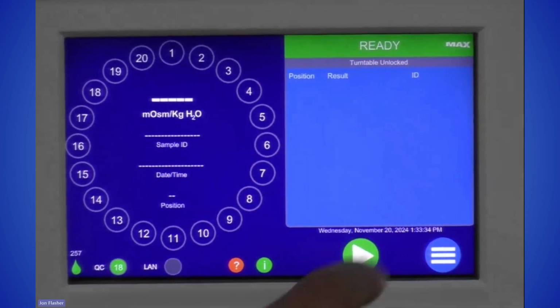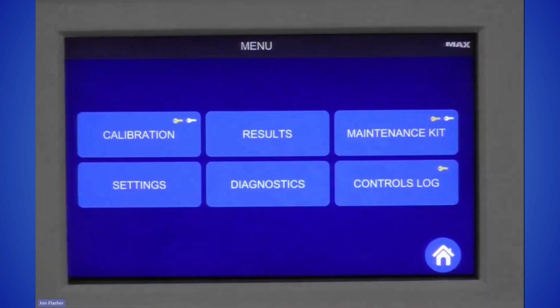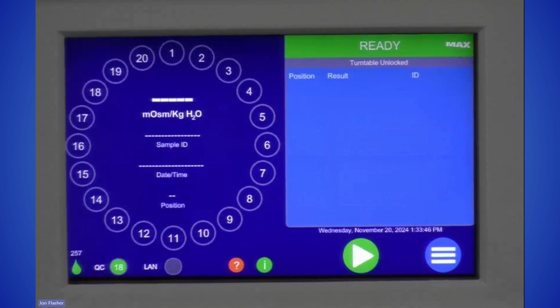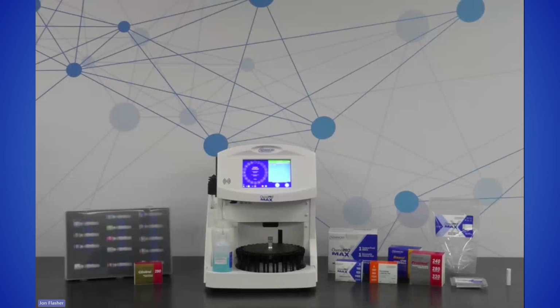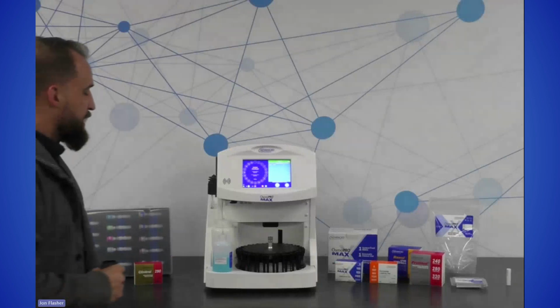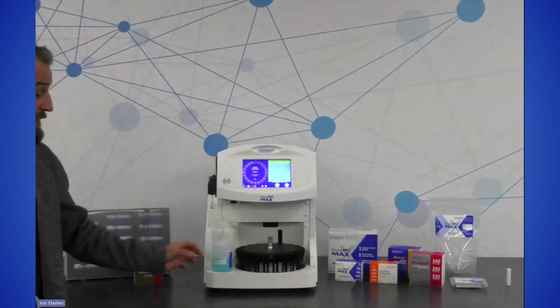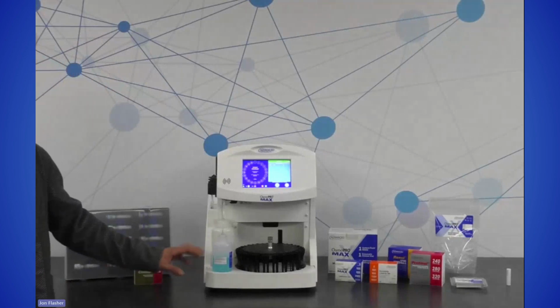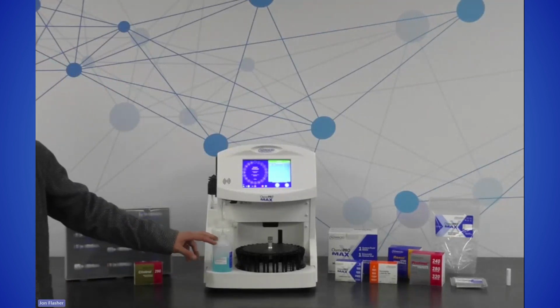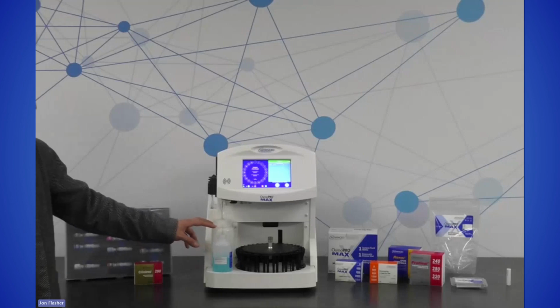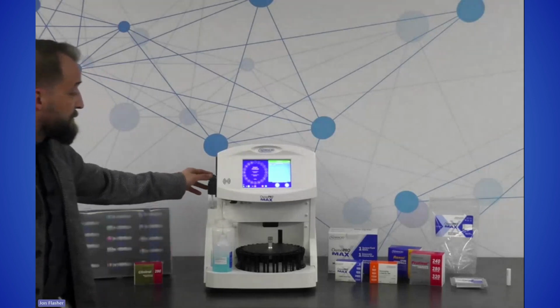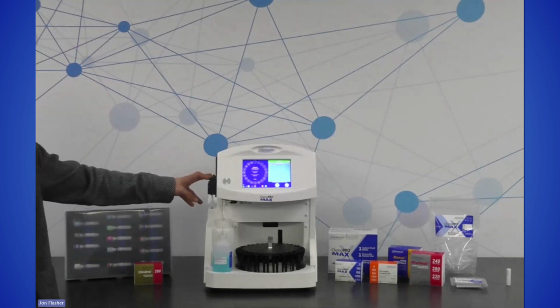And a similar feature is accommodated by the maintenance kit process. Again, once you start that, you can't stop it. But once you go into that, it does give you a frame-by-frame instruction of how to perform the entire maintenance, 500 test maintenance of the OsmoPRO MAX. And to do that, you're going to do three things. You're going to replace the system fluid, which again is the blue fluid in the front. You're going to empty your waste container. Then you'll replace the peristaltic tubing on the side of the instrument.